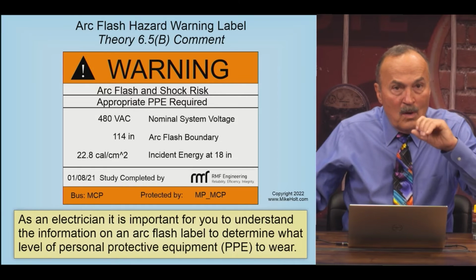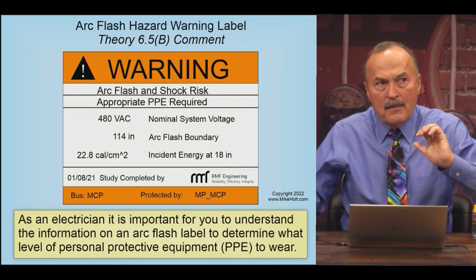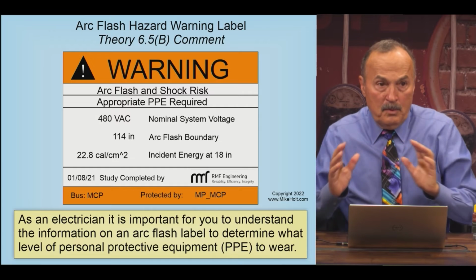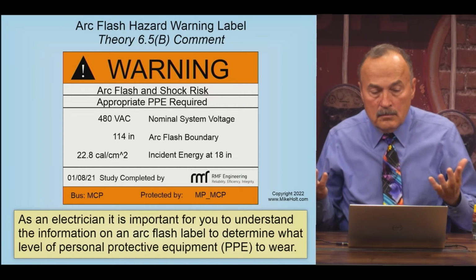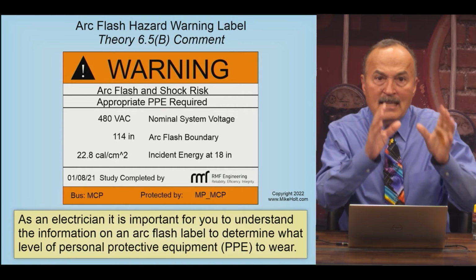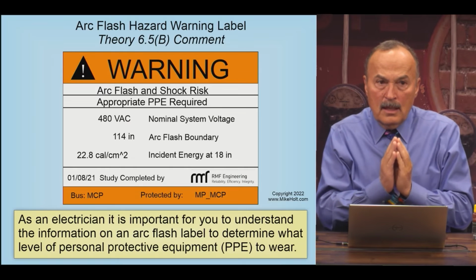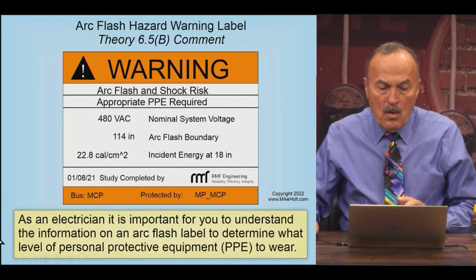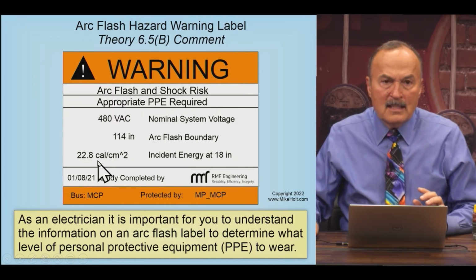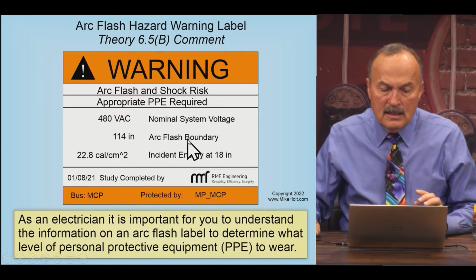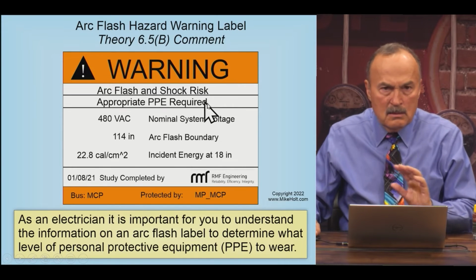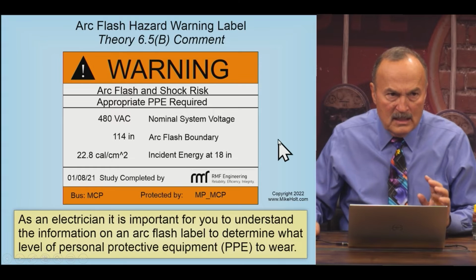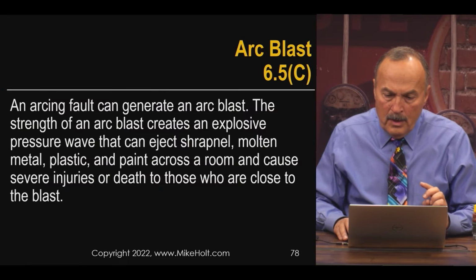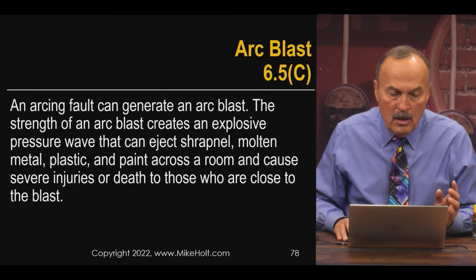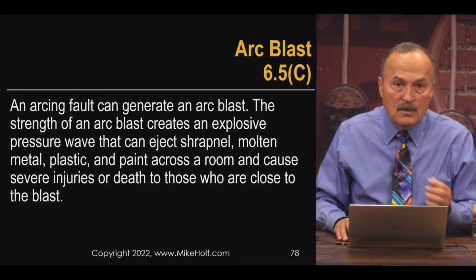So what NFPA 70E says is, and it's not a requirement to put this on equipment, this is just a standard, that if we have the labels, it allows the electrical professional to know we need protective equipment here. It also gives an incident energy and a boundary, which we won't get into in much detail. So an arcing fault can generate an arc blast, which we see, and that's the concussion.